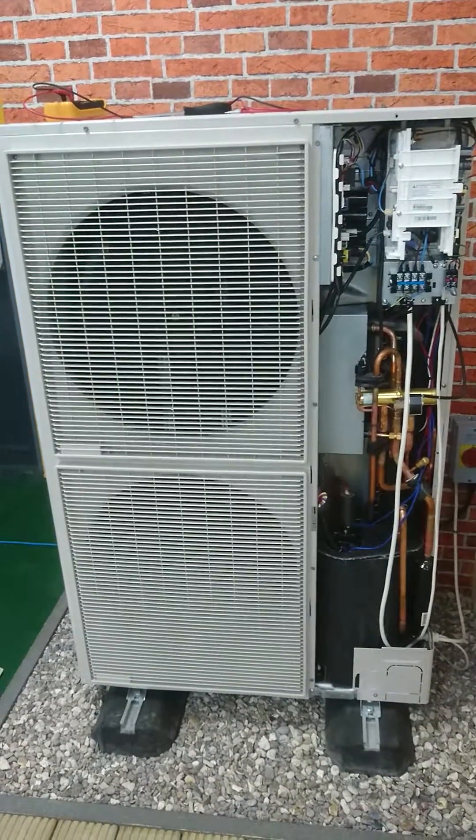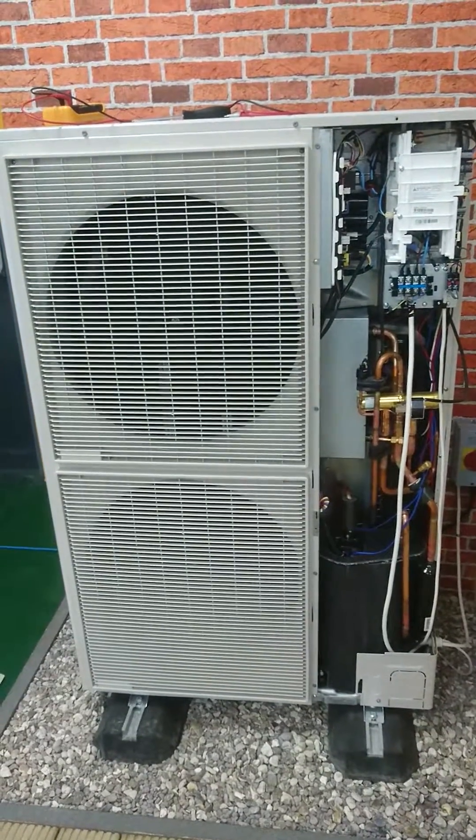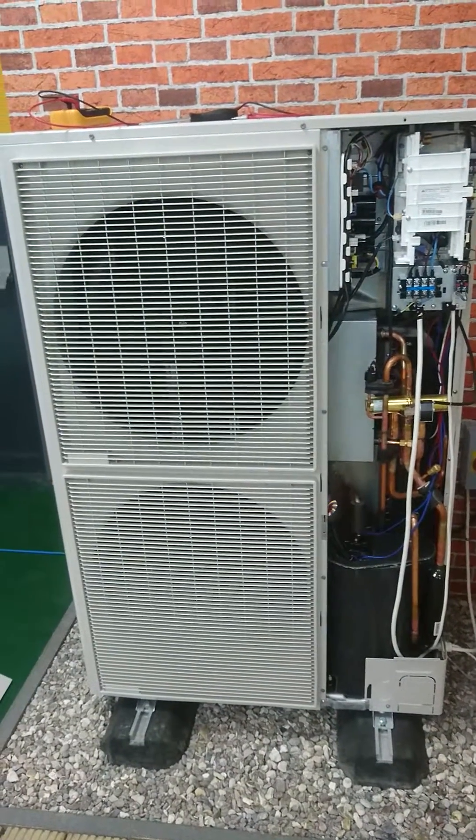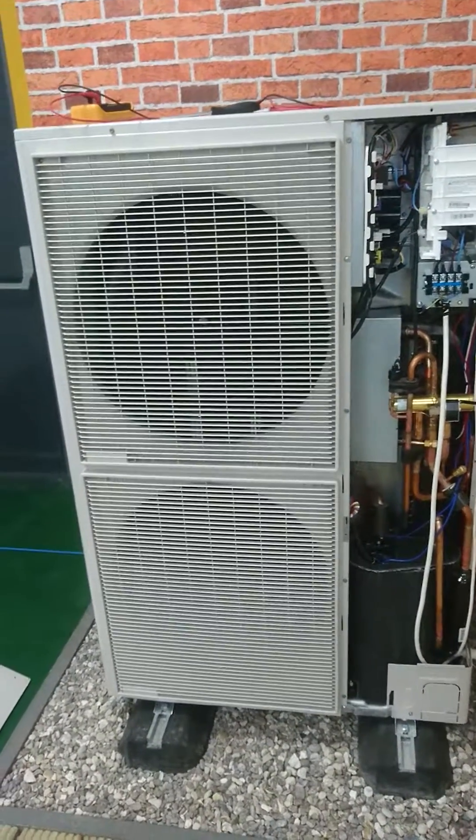In this video, I want to show you fault code E475, which if you look very carefully, you can see that the top fan motor is not running, while the bottom one is.